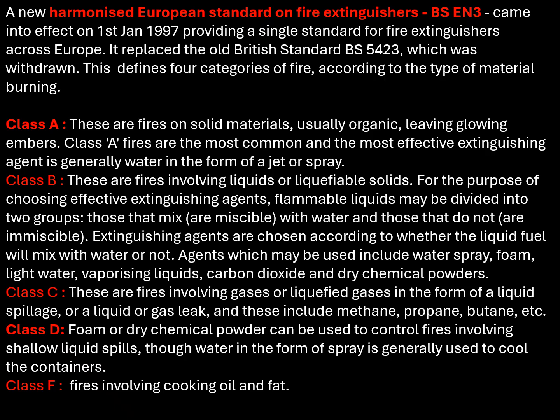This slide provides the detail of a harmonized European standard on fire extinguishers, BS-EN3, which came into effect in 1997, providing a single standard of fire extinguishers across Europe. In this, the first three are the same as we have already learned. Class D is a new type of fire, for which foam or dry chemical powder can be used to control fire involving shallow liquid spills, while water in the form of a spray is generally used to cool the containers. And Class F, of course, is fire involving cooking oil, gases and fats.